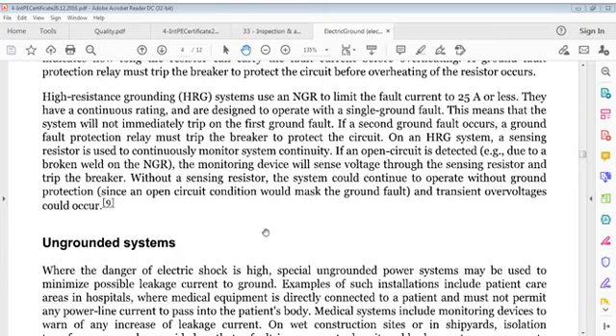So what I say: high resistance grounding, HRG, systems use an NGR to limit fault current to 25 amperes or less. They have a continuous rating and are designed to operate with a single ground fault. This means the system shall not immediately trip on the first ground fault. If a second ground fault occurs, a ground fault protection relay must trip the breaker to protect the circuit.